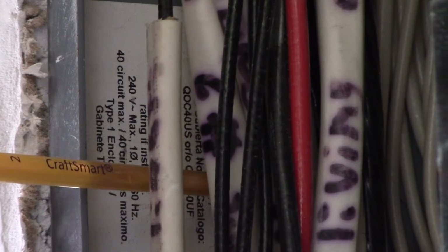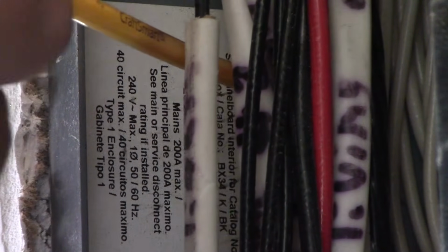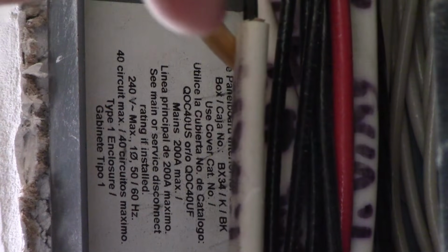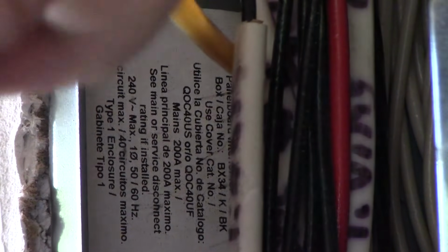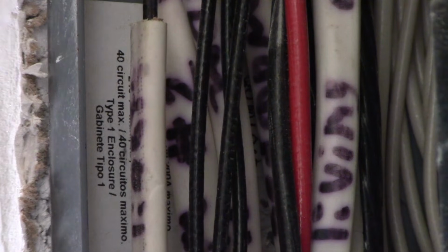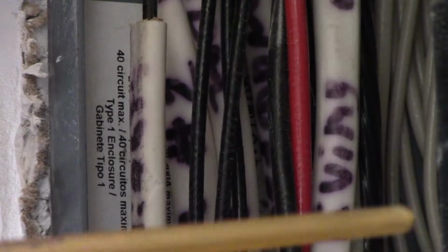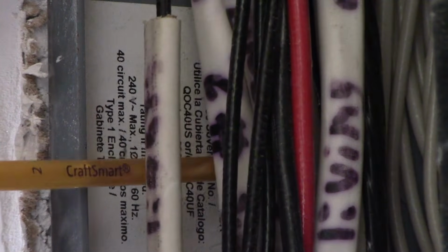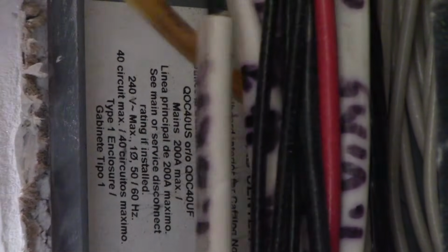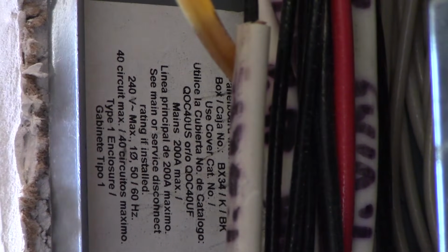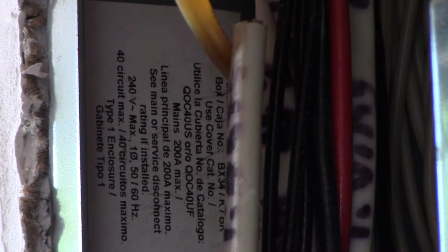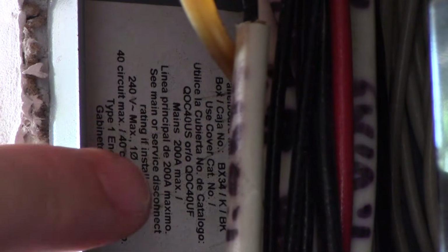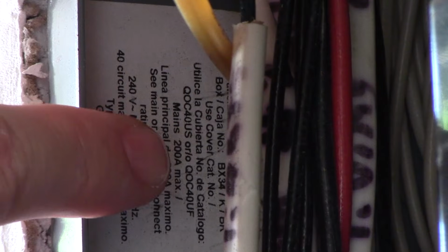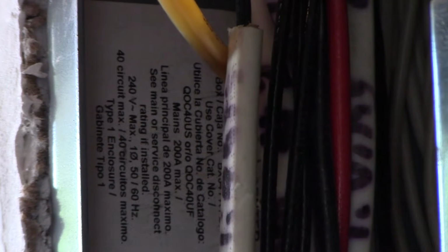Okay, now we're on the left side of the cabinet, and we have an enclosure here that actually has some labels. Now, you're not always going to have this luxury when you're dealing with older panels, but this panel we do. If you're looking here and you use your non-conductive probe, and this is the primary use for this non-conductive probe, is to be able to slide it in here and slowly pry away a little bit in order to be able to read these labels. And in this case right here, we can see that this load center is rated for 200 amps, and that's what we see located here.